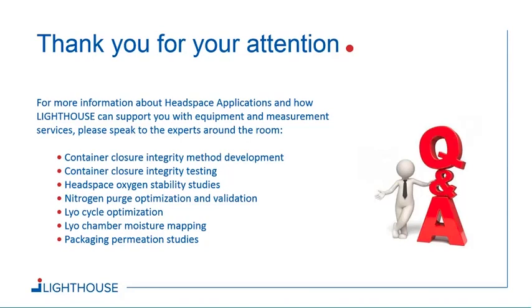And we'll see if that language stays in the revised Annex 1, but that is the indication that we're getting from them. If they enforce that, then I think that will actually be a significant impact on best practices, because with the standard methods that are currently used, blue dye testing, microbial ingress testing, it's very, very challenging to produce statistical CCI data that give you insight into your process.